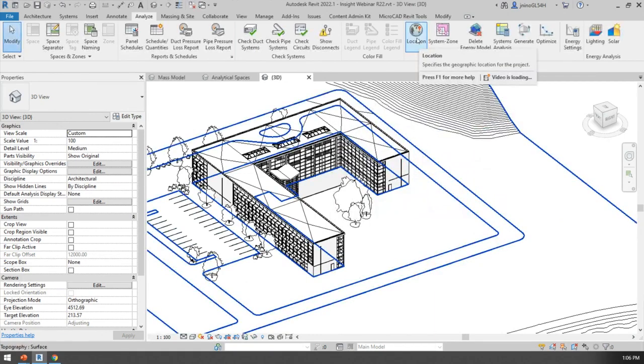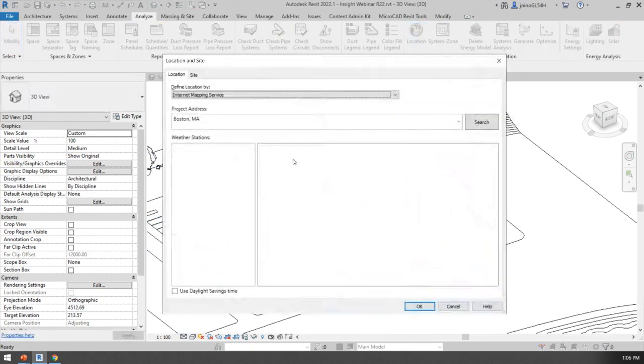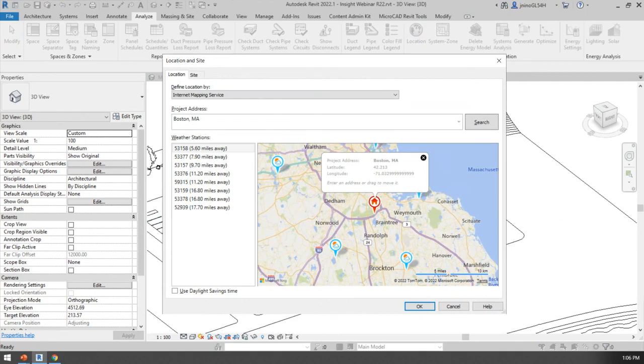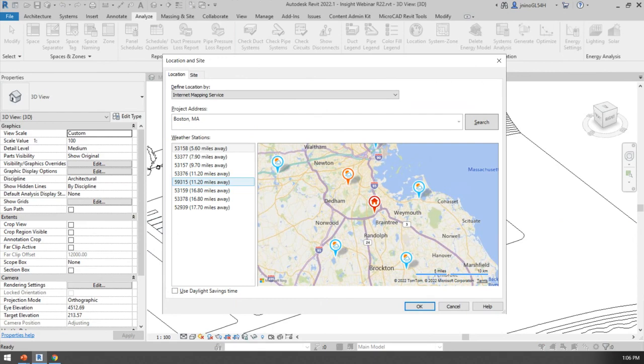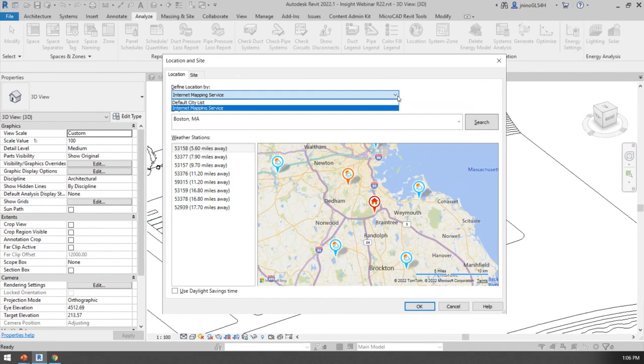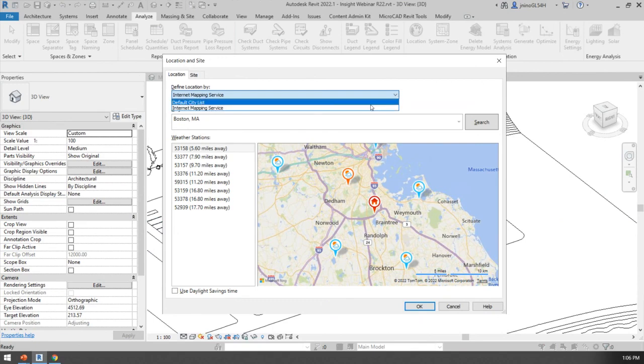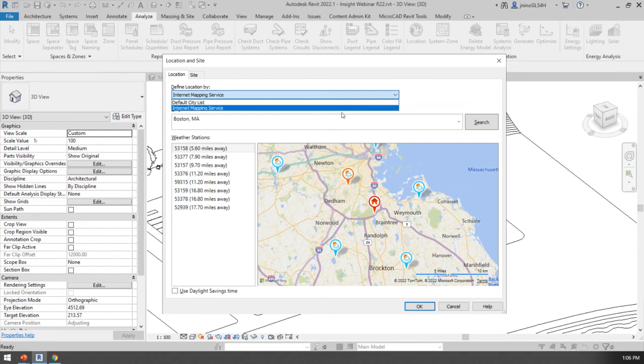The first thing you want to make sure you have set up is your location. With the location set, you can use real-time data from your project's location, including weather files. You have two options: the default city map list or the internet mapping service. The main difference is that the default city list is for HVAC sizing analysis, while the internet mapping service should be used for energy simulation and calculating heating or cooling loads.